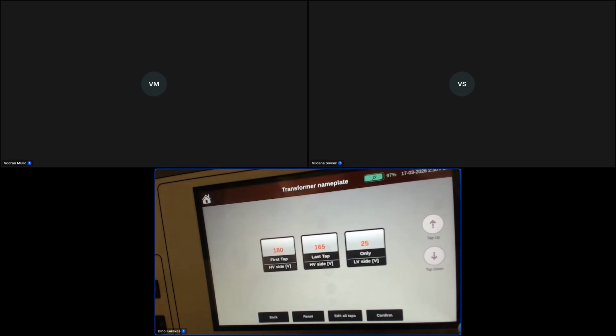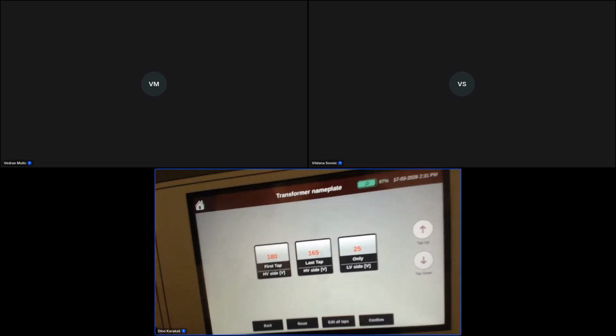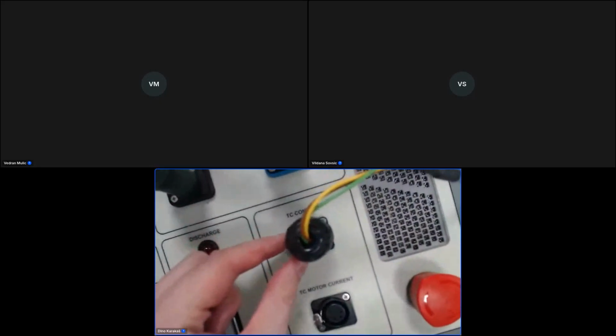And here you can change the tap position of the transformer. If you came to the field, you want, of course, to test from the first tap position to 25th, for example, and you came upon the transformer which is in 13th tap position, you can go tap down, tap down, tap down until the first tap position. To enable this feature, you need to have this tap changer control cable connected to the tap changer box on the transformer. This cable is part of the standard accessories.